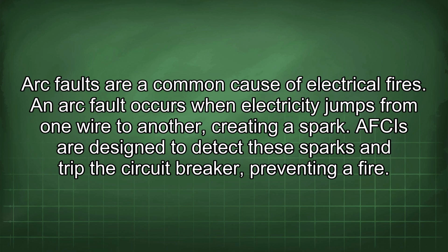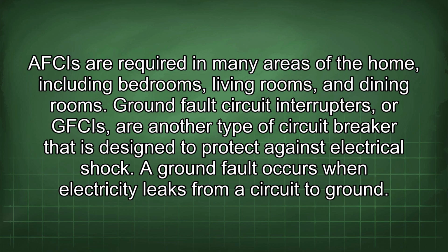Arc faults are a common cause of electrical fires. An arc fault occurs when electricity jumps from one wire to another, creating a spark. AFCIs are designed to detect these sparks and trip the circuit breaker, preventing a fire. AFCIs are required in many areas of the home, including bedrooms, living rooms, and dining rooms.